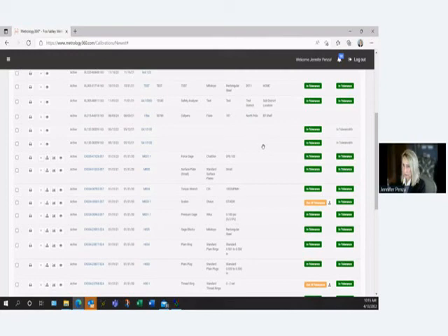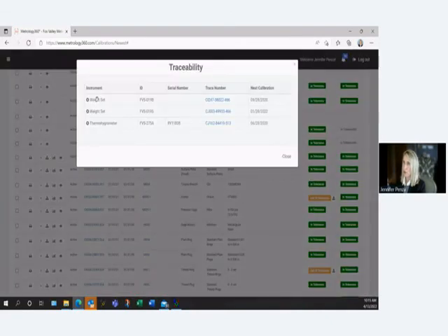The next thing that I want to show you is this little traceability chart. The traceability chart is really good for anytime you're having an audit. It's going to show you all the measurements and test equipment that Fox Valley Metrology used when we calibrated your gauge. Our ID numbers, the next calibration due dates, and our actual certificates can be viewed right here.